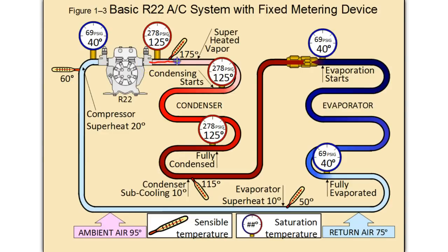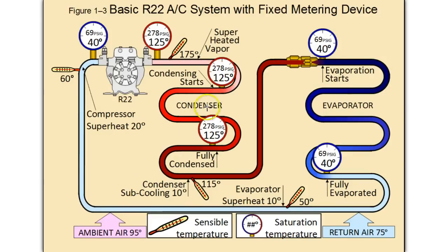As the high pressure, high temperature superheated vapor enters the condenser, it will start to condense. The part between the point it enters and the point it condenses, it desuperheats — shedding sensible heat. It's getting rid of that 50-degree difference between the 175 it actually is and what it should be at its saturation point. At a certain point in the condenser, it reaches its saturation point, and as heat is removed it changes state from vapor to liquid. At that point it is still at 278 psig but now at its saturation temperature of 125 degrees Fahrenheit.